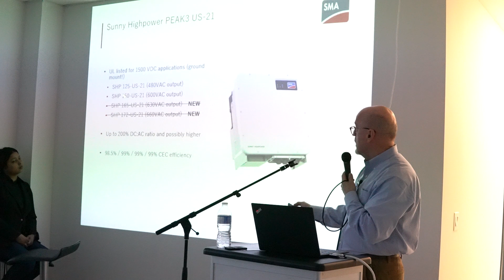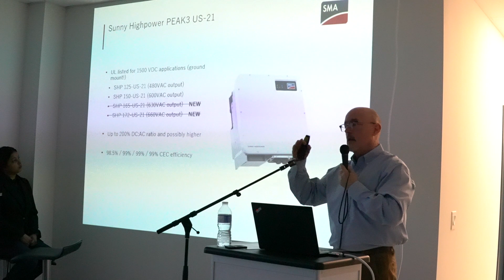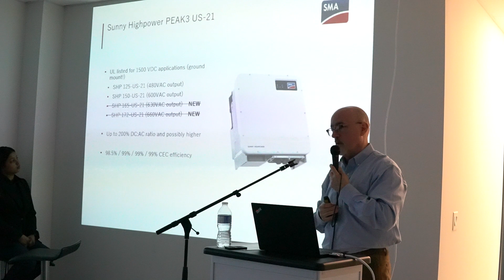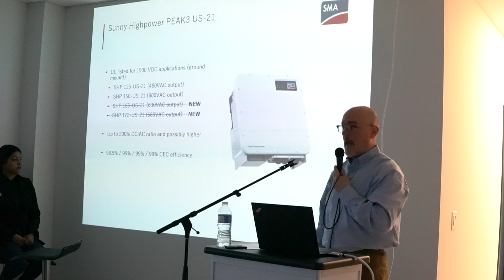Now I show these 2 here, and the reason I do show these is because we announced this, but we've decided these just don't make sense in North America. So unless you do a special order, we're not going to be offering these because of the AC voltages just don't make sense in North America, whereas these are the 2 AC voltages we typically see. So the 125 is 480 volt AC, whereas the 150 is 600 volt AC. And the advantage here versus central inverters is a building block approach. First of all, it allows from an operations and maintenance standpoint, much simpler operations and maintenance. From an installation standpoint, much simpler. And if you have a failure, you're not losing the whole, multiple megawatt central inverter. So some real advantages here.